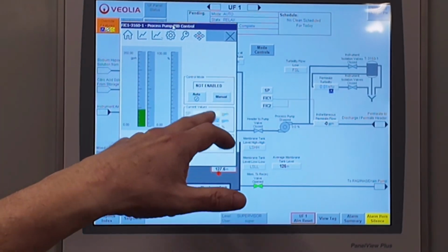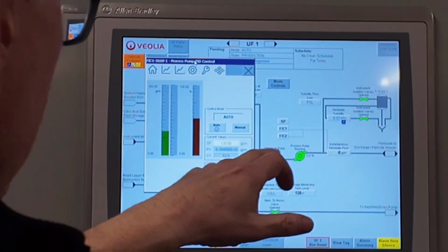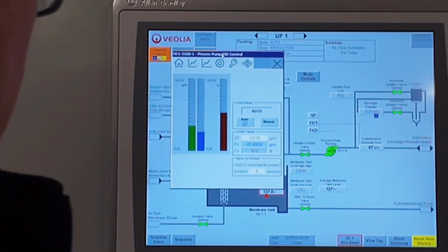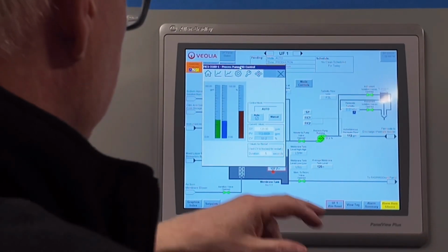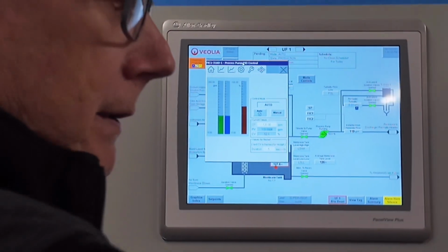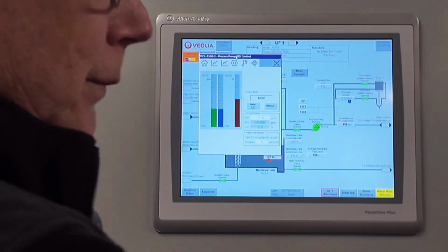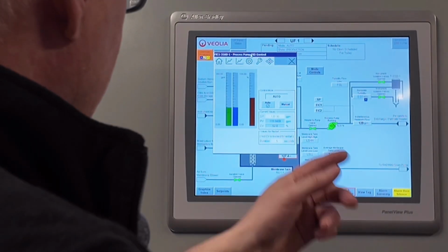So right now there's no set point, because now we go to production, the valve opens, set point's 120, and it's going to ramp up. I'll see that it just went 115, 112, so that's pretty smooth. It didn't overshoot it, and then I'll just slowly crank up. So it's a pretty nice curve there, no sine curve going on there. And then we're back up to our flow.